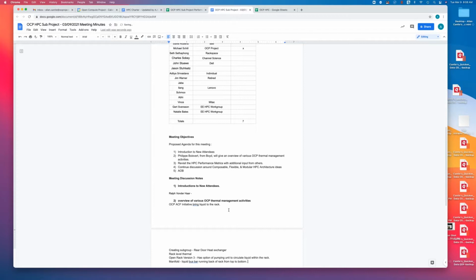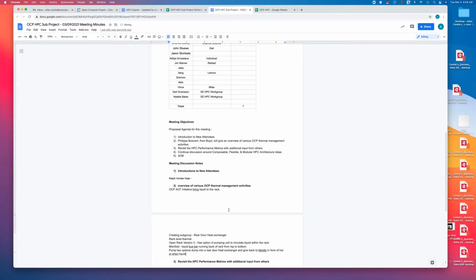And then the pump has two options. It can dump the heat from the hot liquid into a rear door heat exchanger and give the heat back to the facility in the form of hot air. That is for existing facilities that do not have liquid brought to the rack. Or later on, the pumping unit can exchange the heat directly with the facility liquid, if it is available at the rack level.